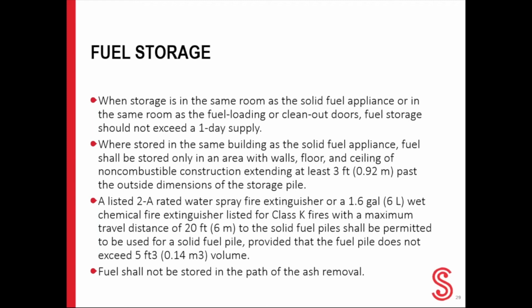There are 3 approved protection methods, and they are 1, a 1.6 gallon Class K or 2A rated fire spray extinguisher. It needs to be within 20 feet of the solid fuel piles, as long as the fuel pile does not exceed 5 cubic feet in volume. As a reference, 5 cubic feet is similar to the size of a large residential chest freezer that you might have in your house. 2, a sprinkler system that meets NFPA 13, or 3, where acceptable to the authority having jurisdiction, a fixed water pipe system with a hose that has an adjustable nozzle that is capable of reaching all parts of the area with water spray.